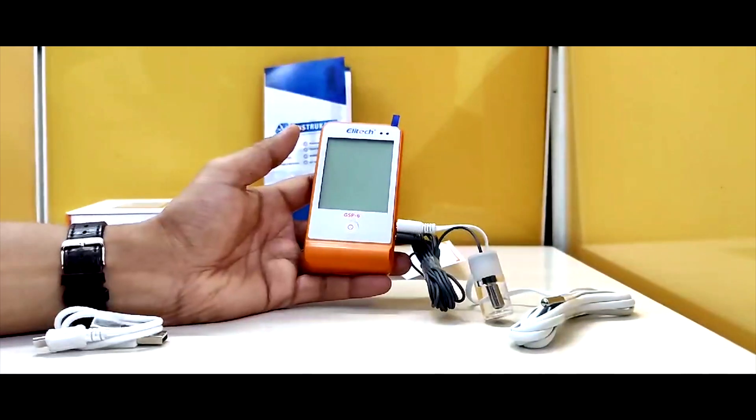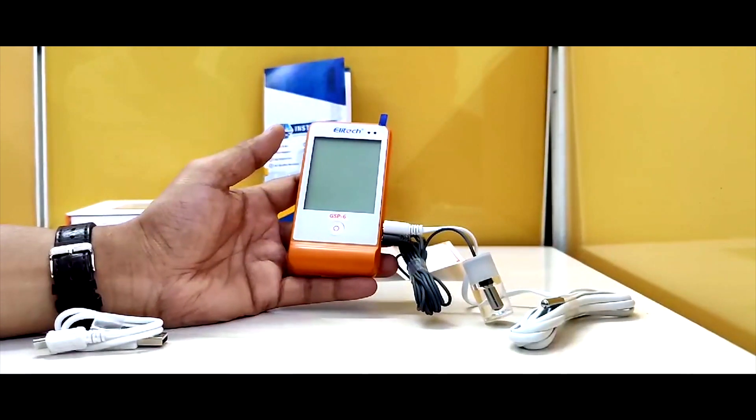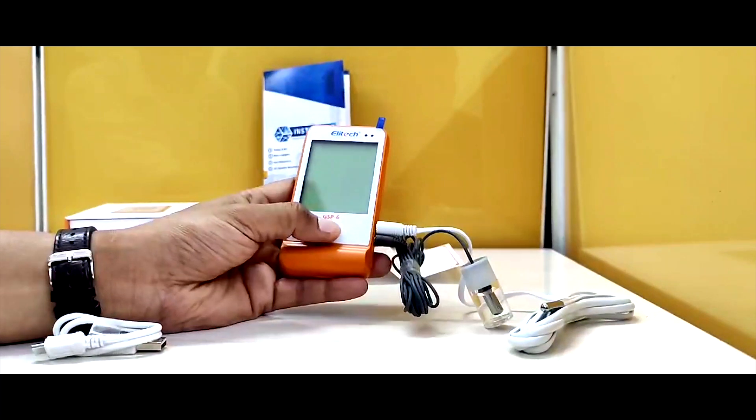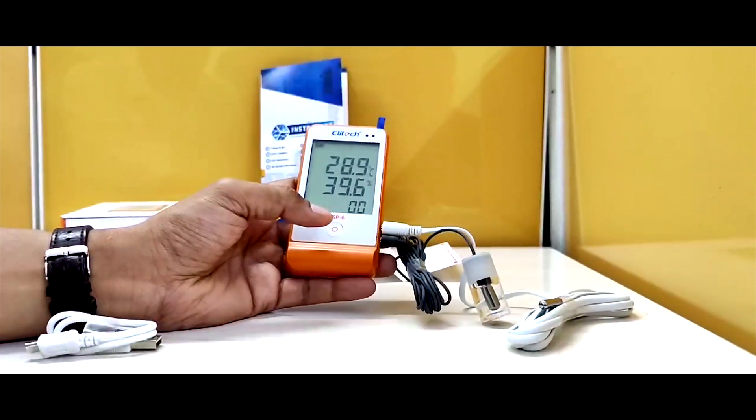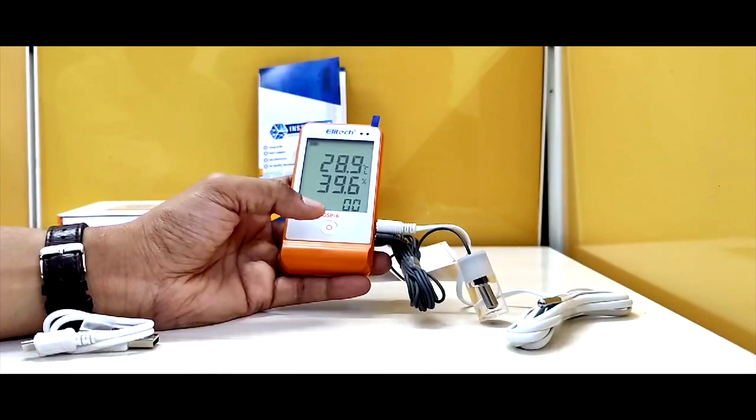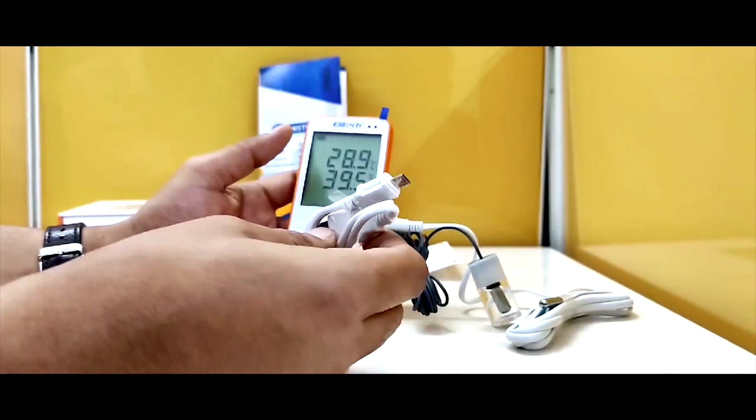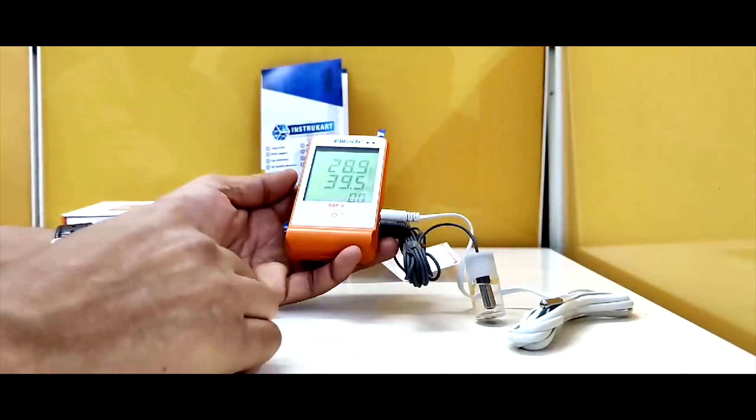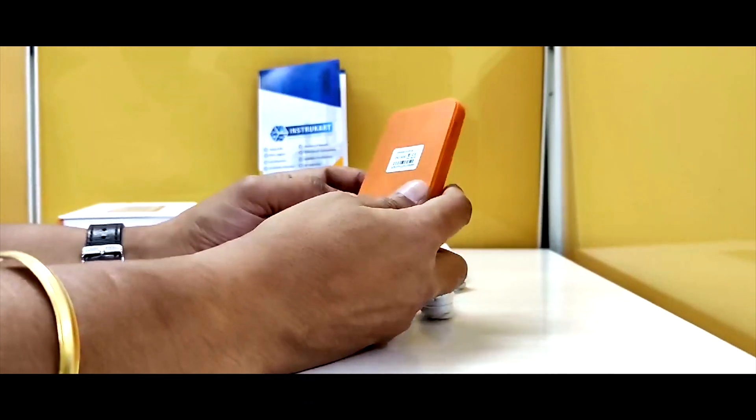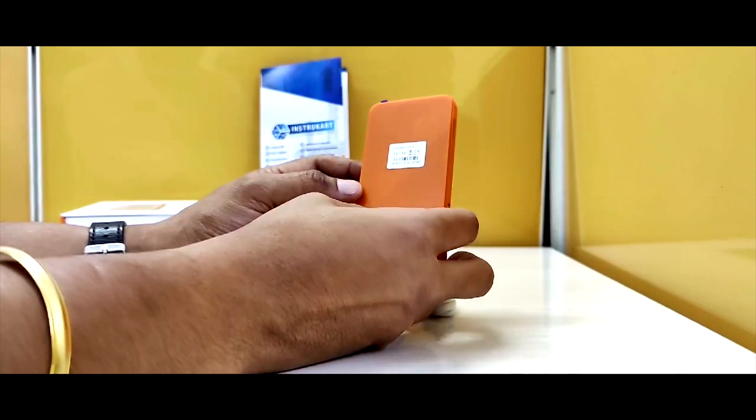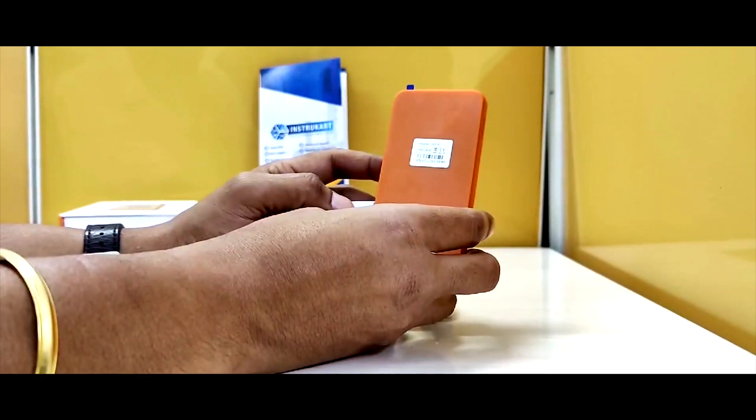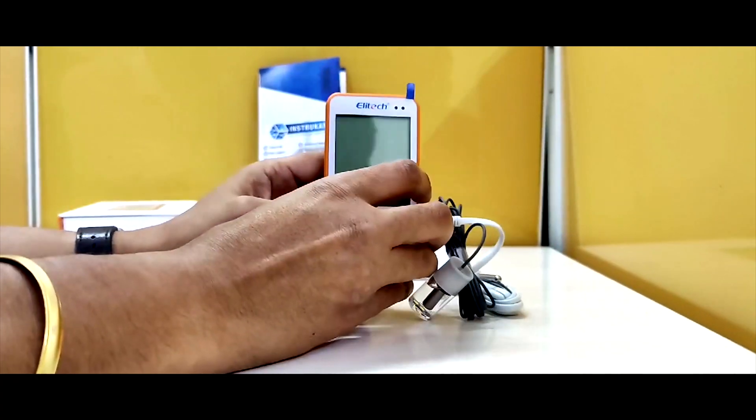We can do the logging intervals from 10 seconds to 24 hours, and the alarm is also available which will give visual and audio alerts. It has an interface to connect to the PC, and for the battery it takes the ER14505 battery or can be powered by USB also.